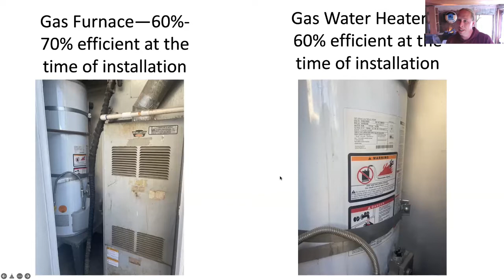I encourage you to think about not putting in electric resistance. These heat pumps, in our climate in California, do not need any electric resistance. The reason why is you have a 100 amp panel and you could get by with just like 10 to 20 amps of heating and cooling if you don't do electric resistance, which you don't need. But someone might encourage it, and that will make it like 30 or 40 amps. And you only have a 100 amp panel, and it makes a big mess of things. You just don't need it.